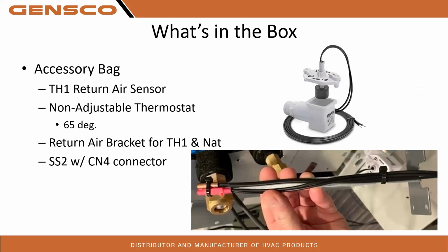A few times I've been seeing guys get calls because they're having a thermostat error after they install this thing. They got these flipped backwards of where they're connected to the unit. The unit does not like to try to read the non-adjustable thermostat for the return temperature. It doesn't work. So if you're coming up with an error after starting it, good idea, check your thermistors, make sure you got them wired up in the right spot.